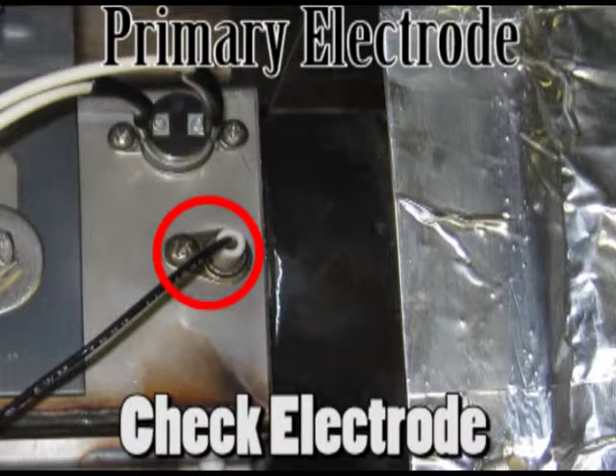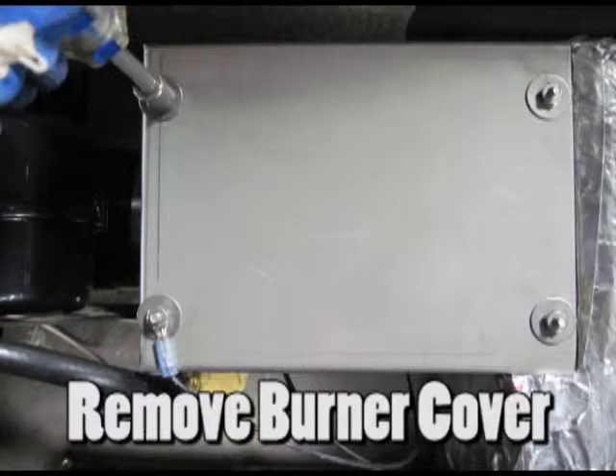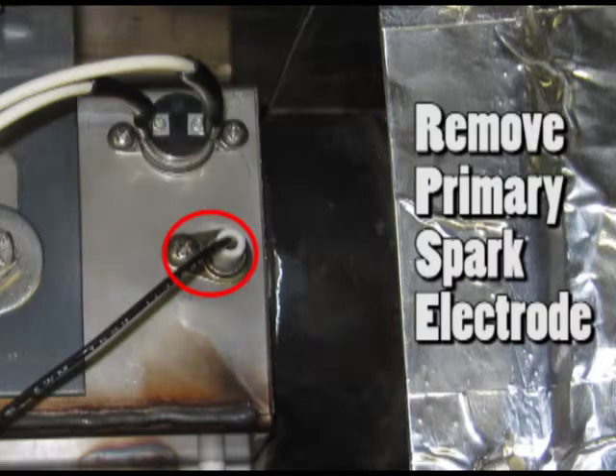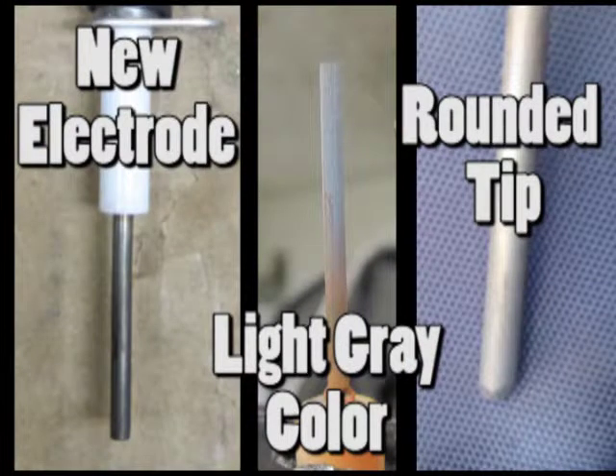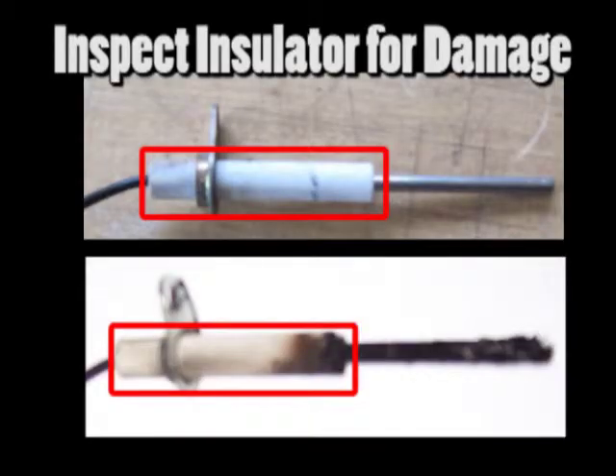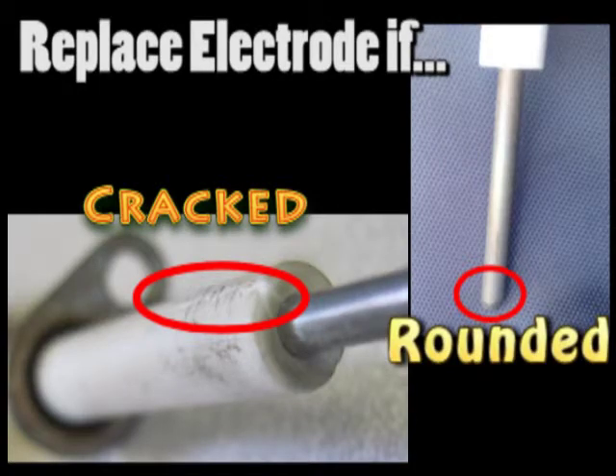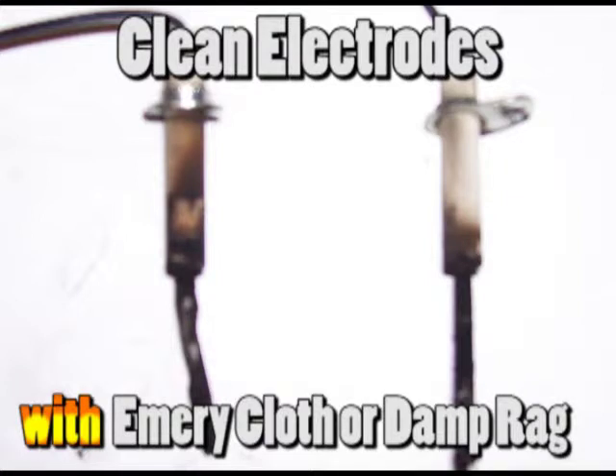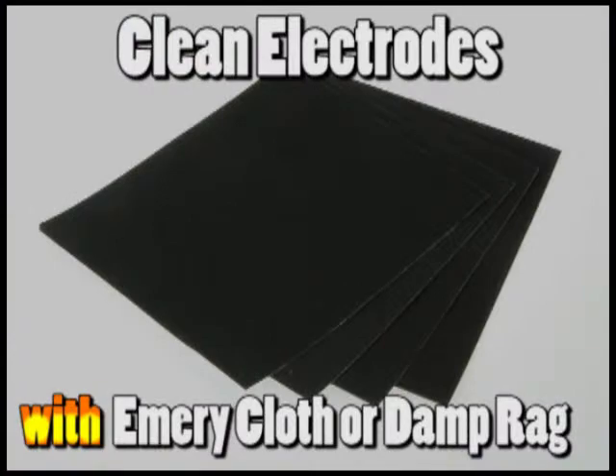Check the primary spark probe. Remove the burner cover from the combustion chamber and the spark probe on the right side of the burner. The metal tip of the spark probe should only be slightly rounded. The ceramic insulator should have only light deposits on it, and the ceramic insulator should be undamaged. If the spark electrodes only have deposits, carefully remove them with a damp rag or an abrasive pad.